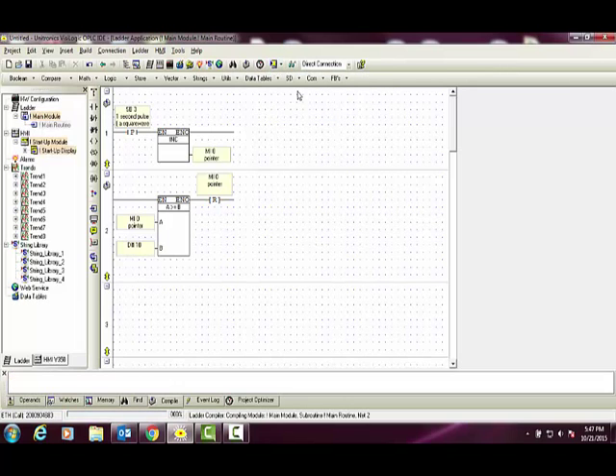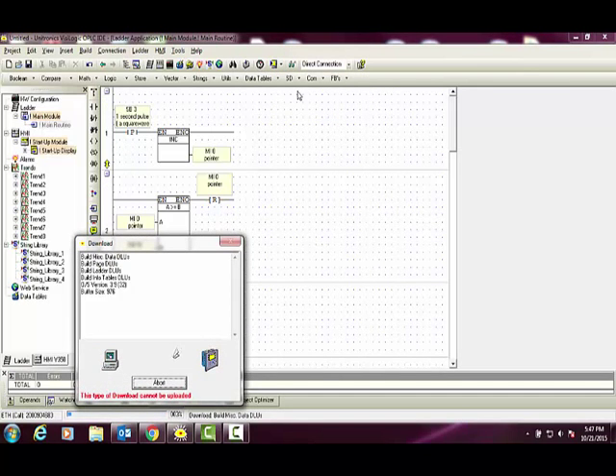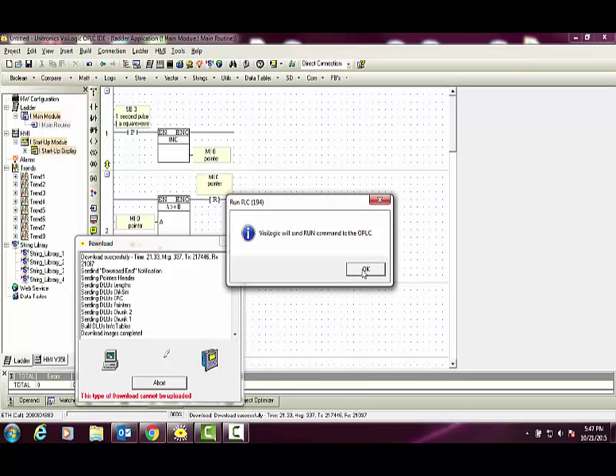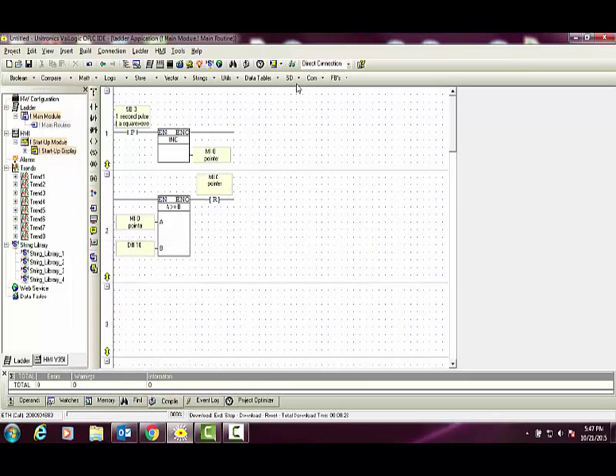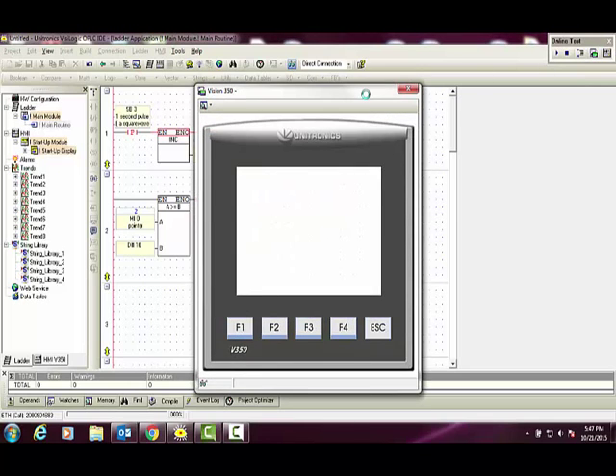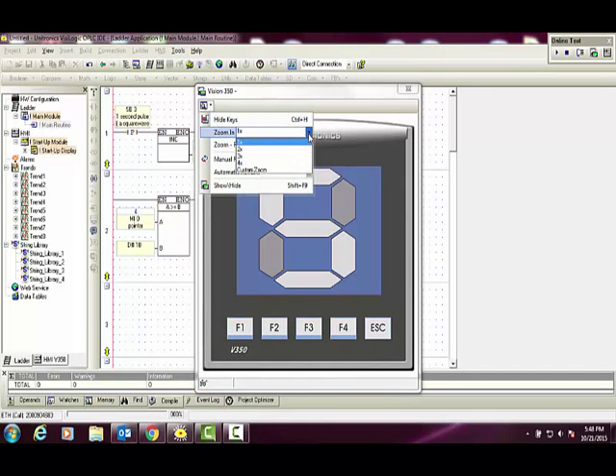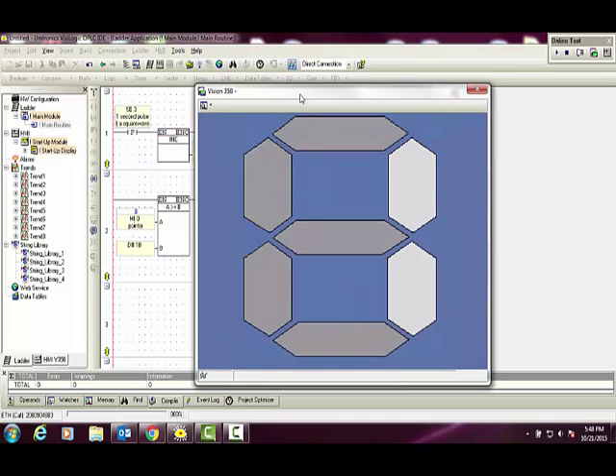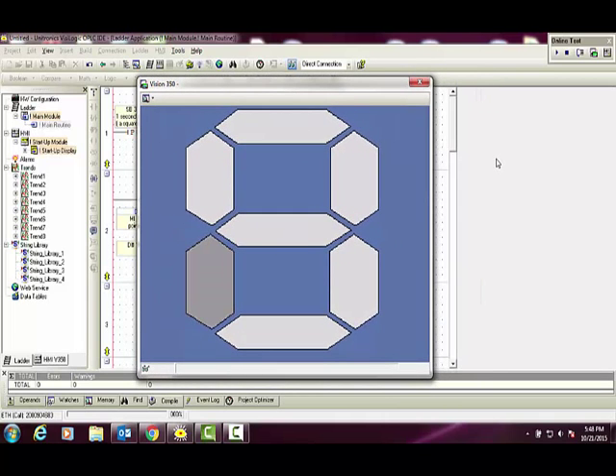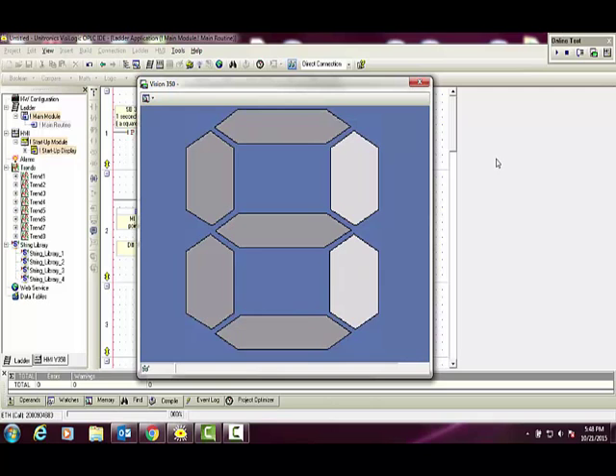If we download this to our controller, select OK to send the run command. And use online test mode to view our HMI. We see that our countdown is running on screen from 9 to 0, and once 0 is reached, the countdown is starting over again.